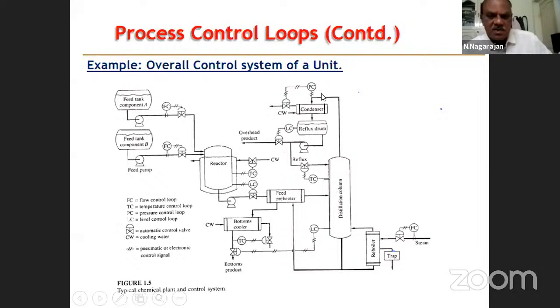So the distillation column has a condenser and reflux drum. Okay, the condenser is operating on the pressure control, and then the non-condensables or uncondensed vapors go out to the vent. The reflux drum operates on level controller. The product is taken out through the level controller, and there is a reflux which is controlled by the temperature inside the column. Okay, so the reboiler has the temperature control. We have seen this earlier, and column bottom flow rate is controlled by the level control here. Okay, this is the bottom product.